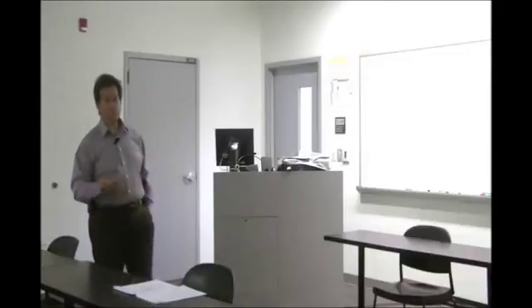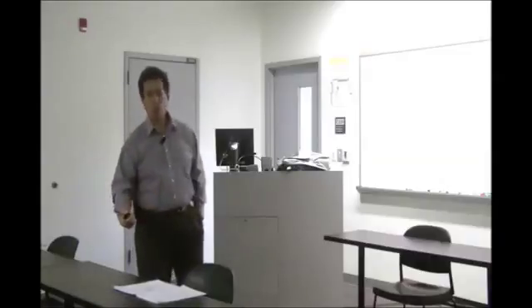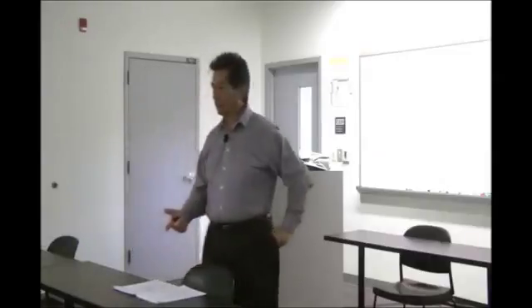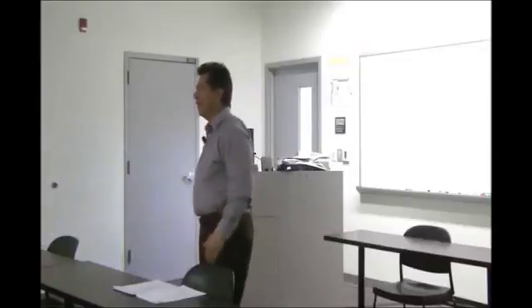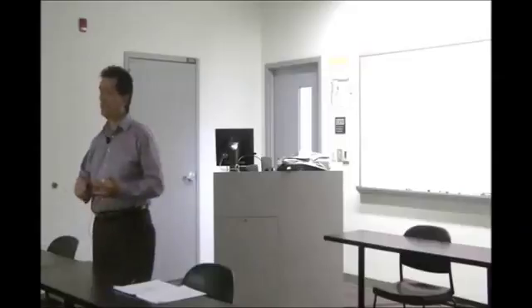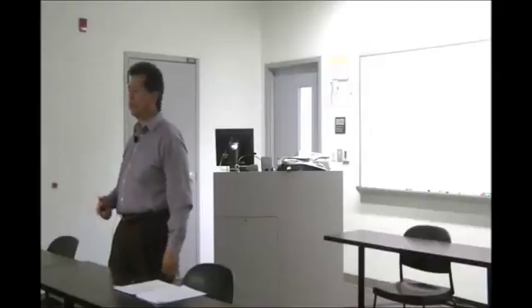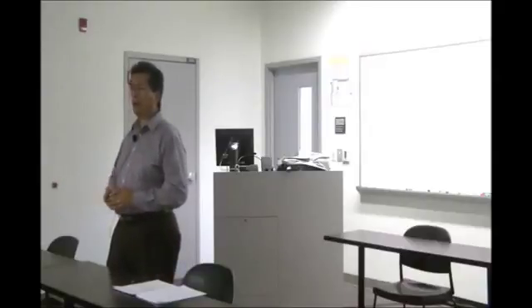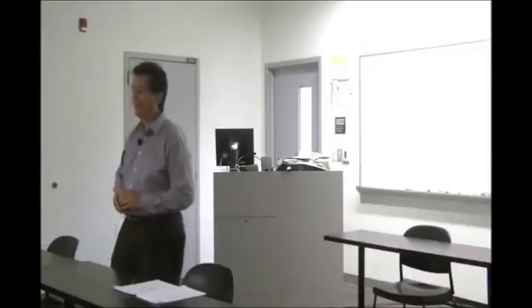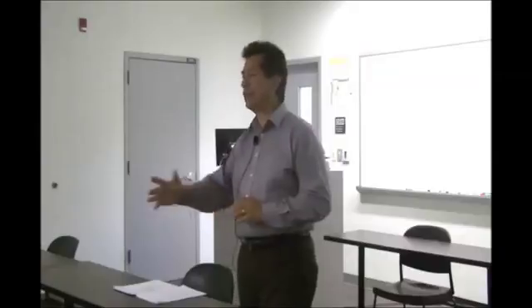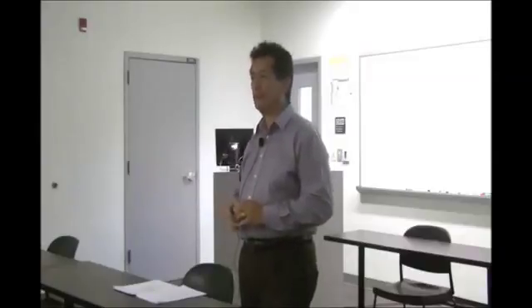Reviewing systems and alarm trends: every morning we get the same cold call from the same room. After 30 calls between 7 and 7:30, it's the same complaint, I'm too cold. You look at your EMS and sure enough, it's 62 degrees in that room. After 30 alarms, wouldn't that tell you something? You think maybe we should go look at it? But you get guys who just go in, ignore the alarm points, forget about it, and it happens again tomorrow. Oh, it's just a quirk, a glitch, it'll clear up next month, right?